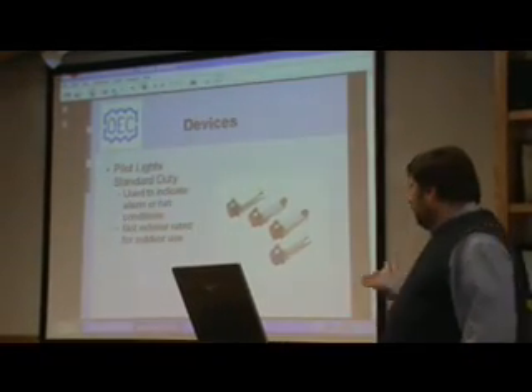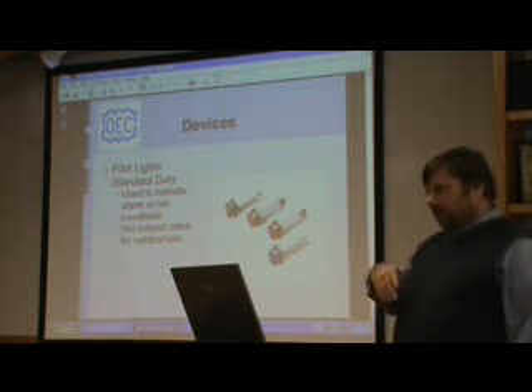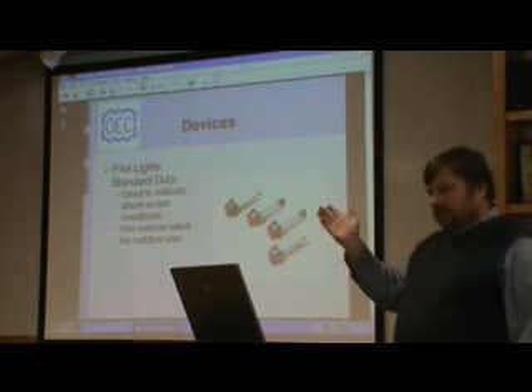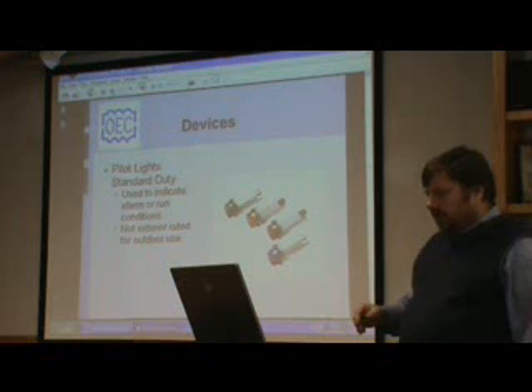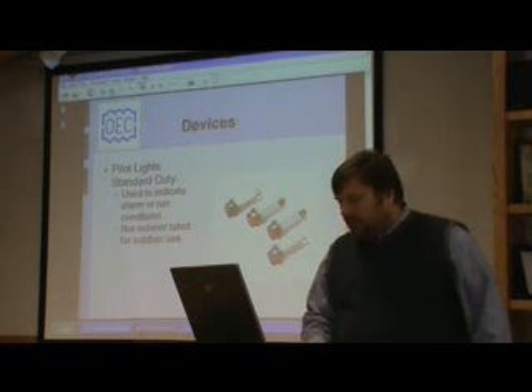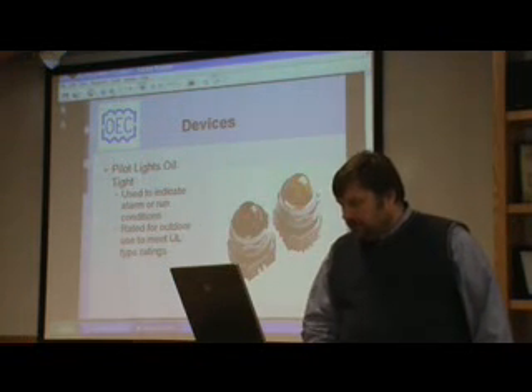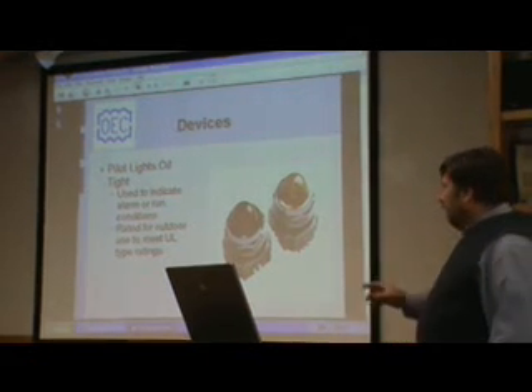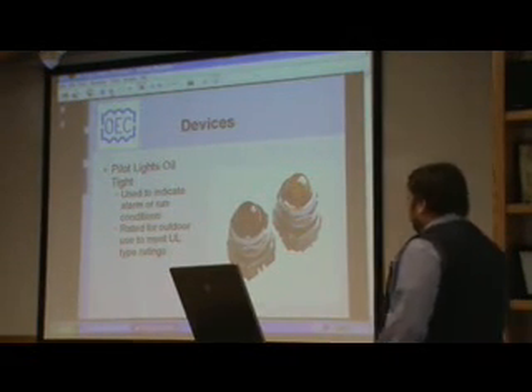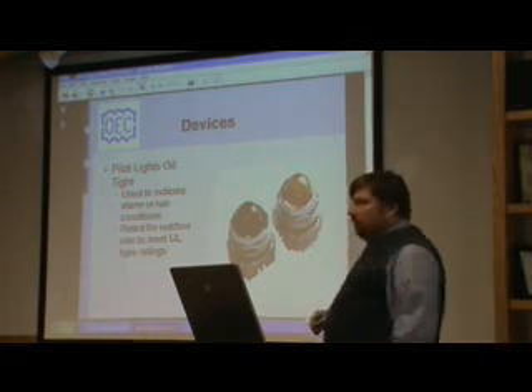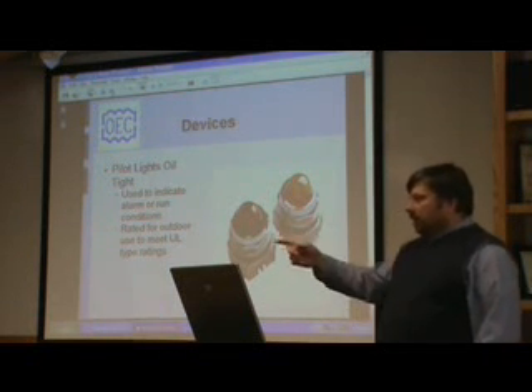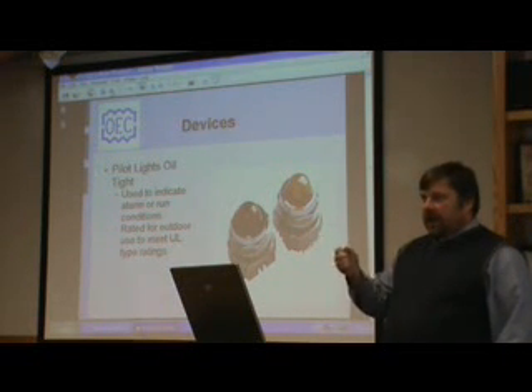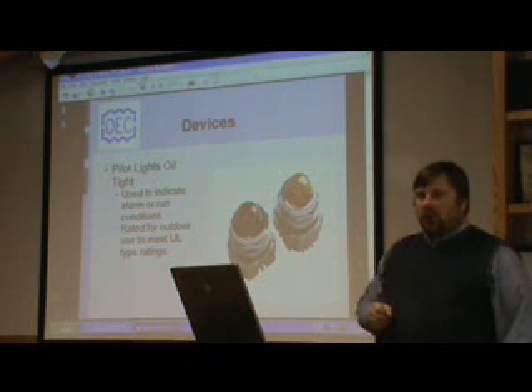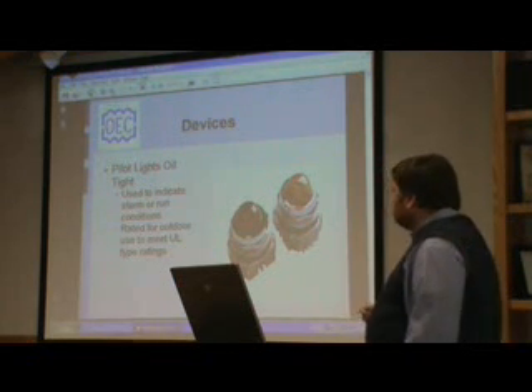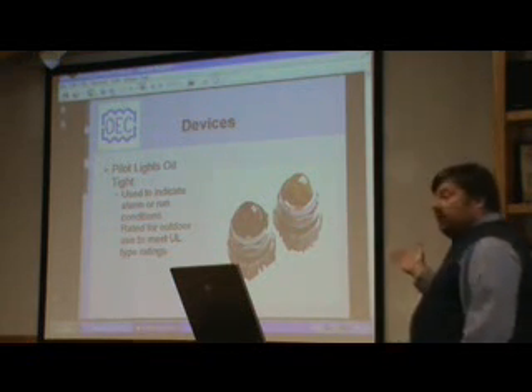They come in a couple different colors like you see, because we have some specs that want green for run, and amber indicates some other thing, alarm that's happening. This is a sample here. It shows you this is the oil tight version. And the oil tight version means that you can mount it through that door and it's going to seal up. It has a gasket that won't allow water or oil to get inside that control panel. Same use as the other lights.